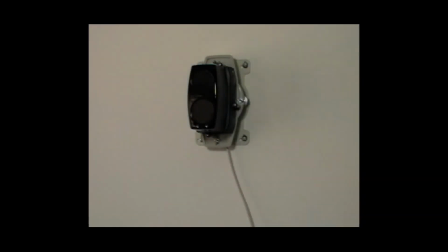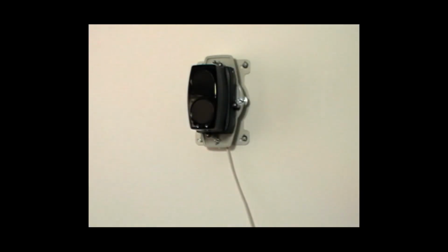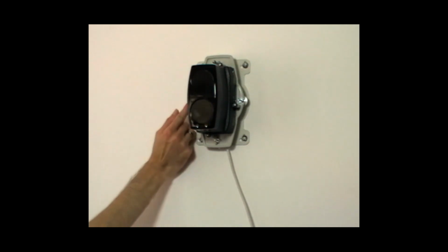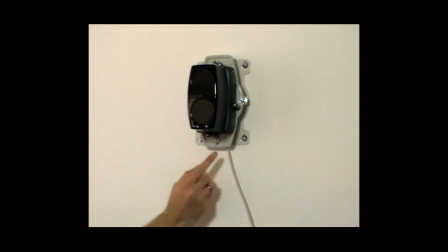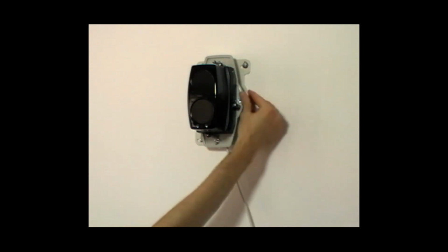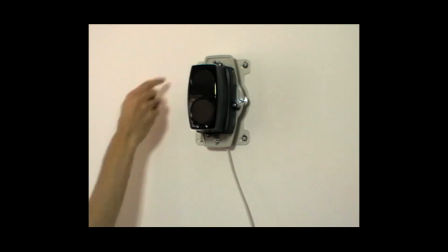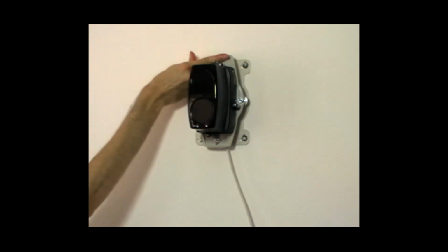You can check the beam detector is centered on the reflector just by touching each edge, then the top and bottom of the detector head. When you touch each side of the detector head, there will be a short flash of the amber LED to indicate beam is slightly off center of reflector, and when released, no LED lights to indicate beam is centered on reflector.